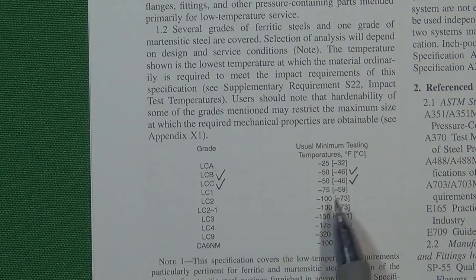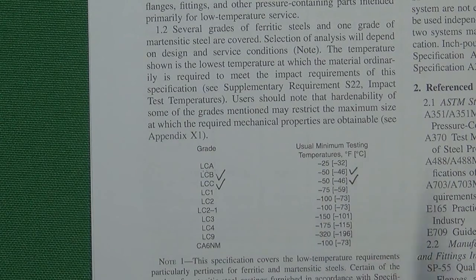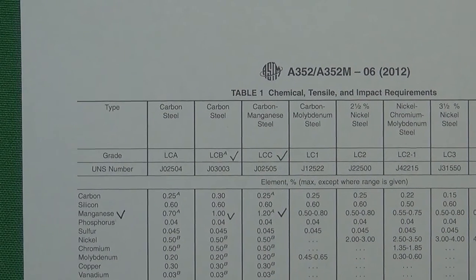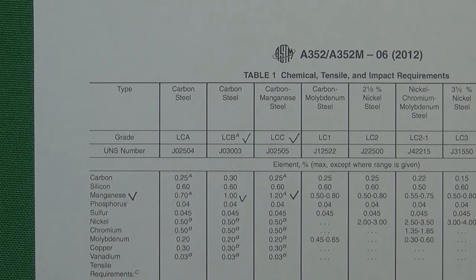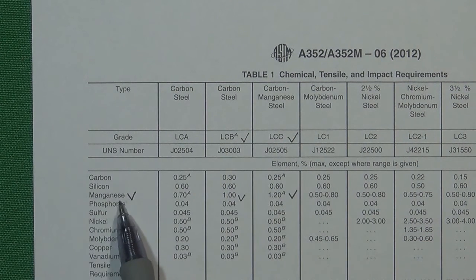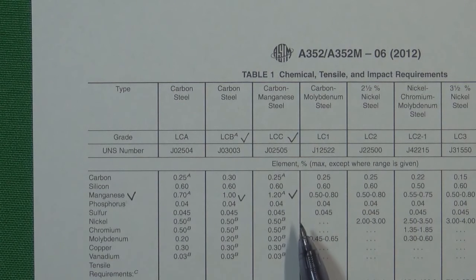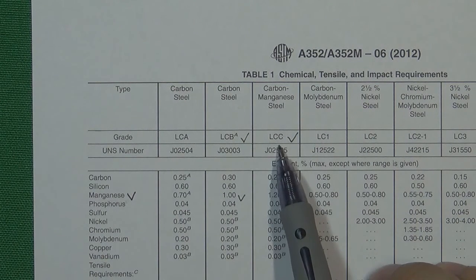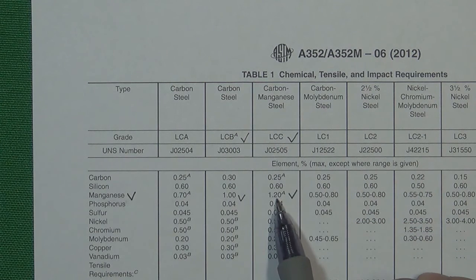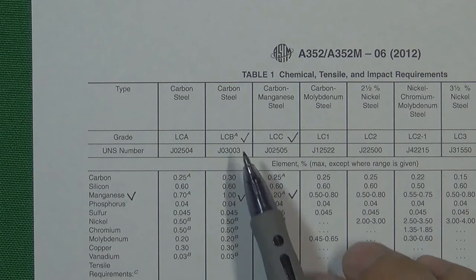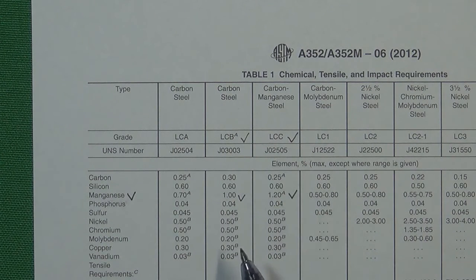So this is also one kind of carbon steel. The minimum temperature for this kind of material is minus 46 Celsius degrees, which equals minus 50 Fahrenheit degrees. The temperatures are not very much lower than the carbon steel minimum temperature, since WCB can work in minus 29 Celsius degree environment. LCB's type is also a carbon steel, containing carbon and manganese inside — very similar to WCB. LCC contains a little bit more manganese compared with LCB, which is a reason why it can perform slightly better in a low temperature environment.